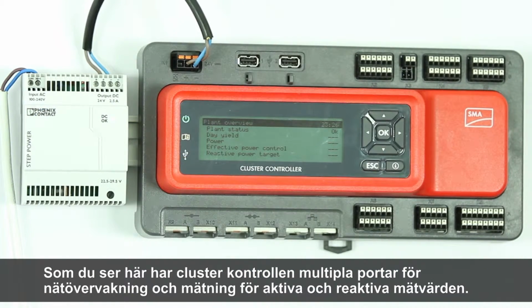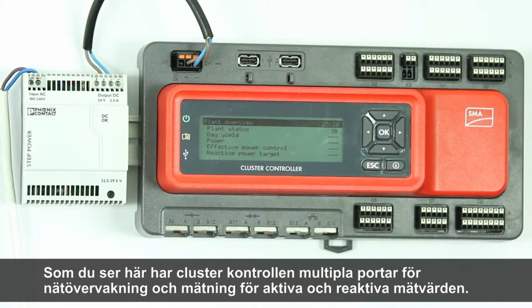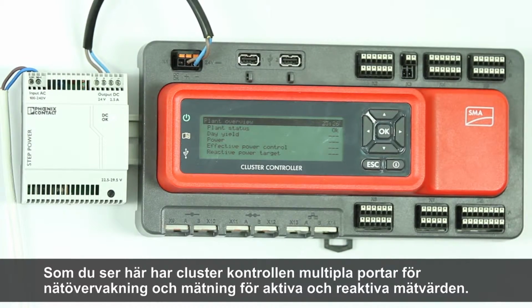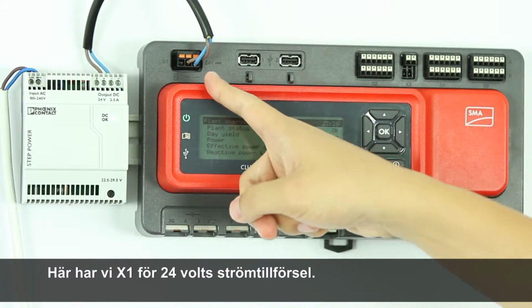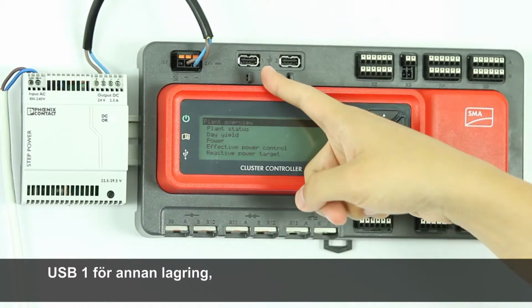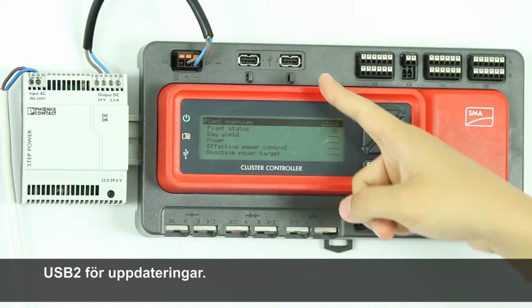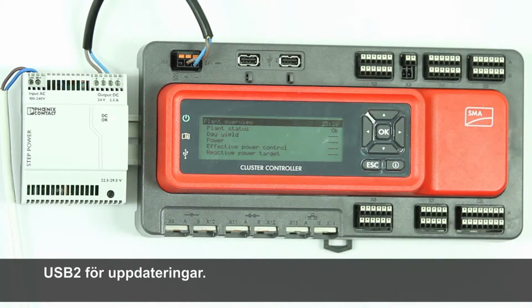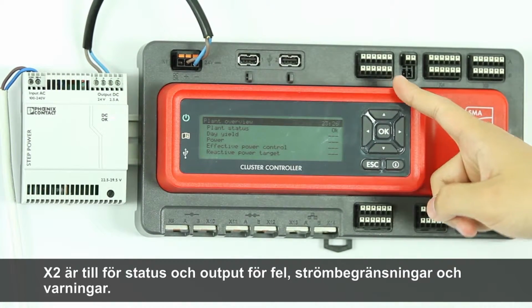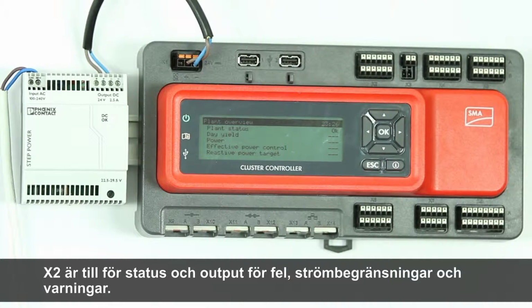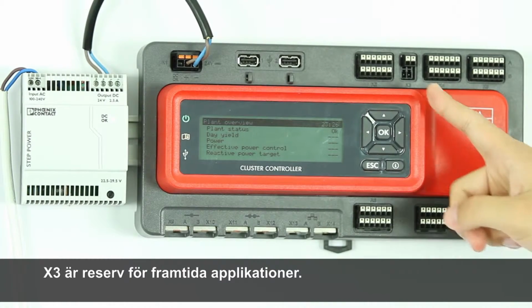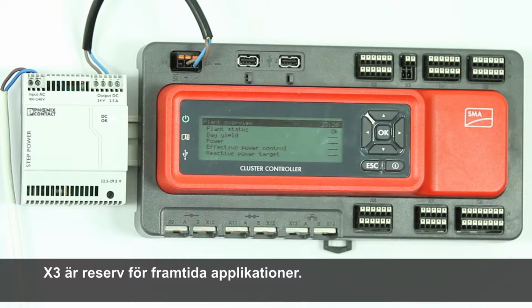As you can see here, the cluster controller comes with multiple ports for sensors and grid management specifications for active and reactive power set points. Here we have X1 for the 24-volt power supply, USB 1 for data storage, USB 2 for updates. X2 allows for 3 digital outputs for status indications on failures, warnings, and active power limitations. X3 is reserved for future applications.